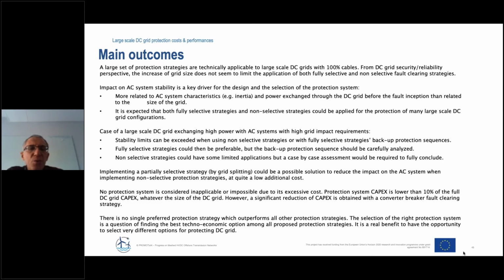Regarding cost, no protection system is considered inapplicable due to excessive cost. We have shown that the protection system cost is generally lower than 10% of the full DC grid capex, whatever the size of the grid. However, there is significant capex reduction if we use a specific non-selective protection strategy with a converter breaker fault clearing approach. We identified that there could be a factor of 2 regarding the cost of the different protection strategies studied: a fast hybrid DC breaker strategy could cost twice the capex of a non-selective strategy with converter breaker clearing.